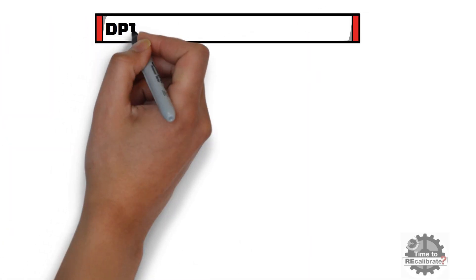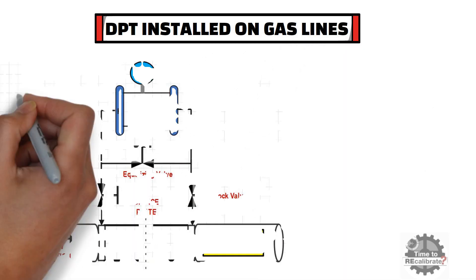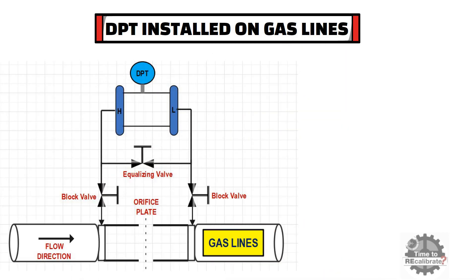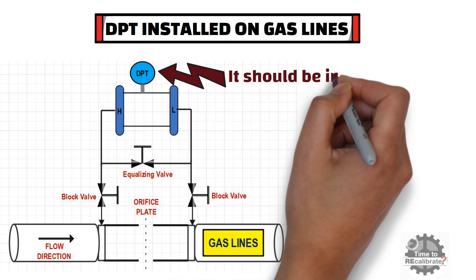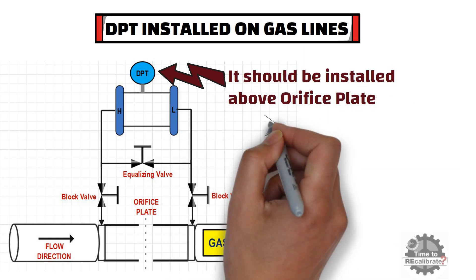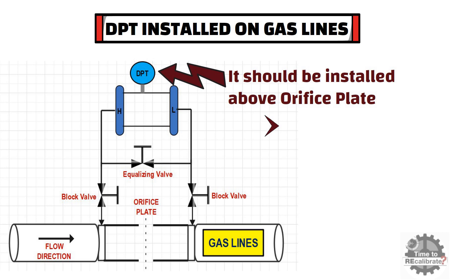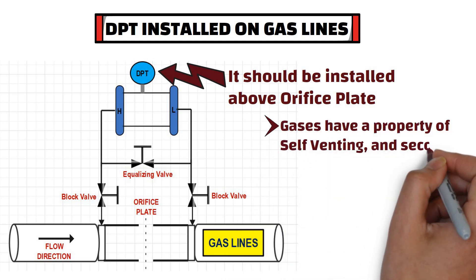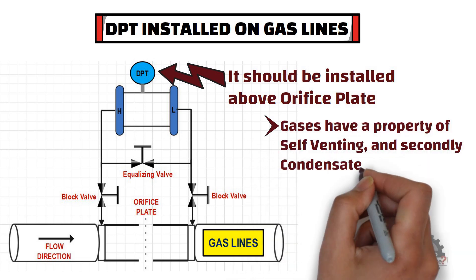Now let's take the situation when a differential pressure transmitter is installed on gas lines. As you can see from the diagram, for gas lines, the DP transmitter should be installed above the orifice plate. The reason behind this is that gases have a property of self-venting, and secondly to avoid condensate formation.